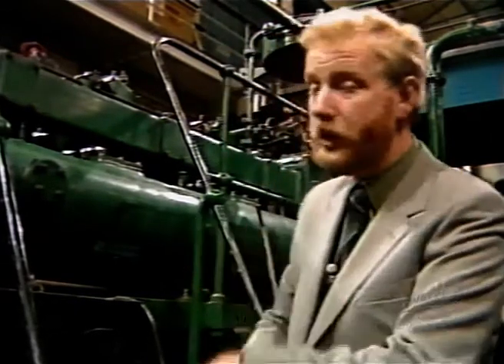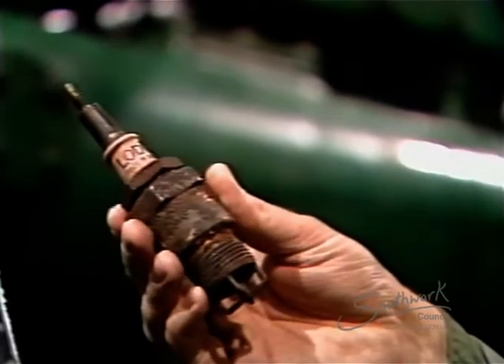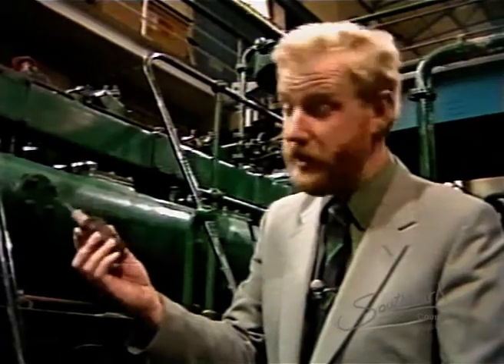Recently overhauled by the local motorcycle repair shop, rotary magnetos on the top of each engine supply the spark for combustion to these huge spark plugs. They're obsolete now, of course, and have to be sandblasted and overhauled when necessary. You couldn't buy a packet of these at your local Halfords. With an engine of this size, you get, as you can imagine, enormous heat. The coolant is water — it's recycled water, a totally closed system, but not a particularly efficient one. Despite their huge size, the cooling area of these towers is quite small, effectively just the top surface layer, so additional cold water is now piped in from the mains at times of excessive demand.